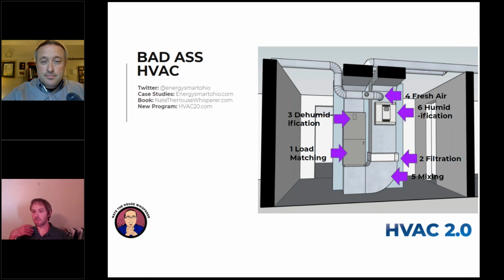And according to this person, they believe it's complex to tie in HRVs and ERVs into existing systems. So they're saying, wouldn't it be better to use it as a low electricity ERV or HRV that's separate? You could, but what's low when we're talking 15 or 20 watts with the air handler? You're going to spend $2,000 on one of those extra when you're talking $250 in parts for doing this. You can, if you want to drive up the amount of airflow that you have, you can do that.